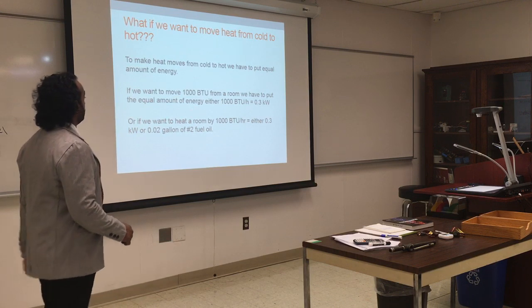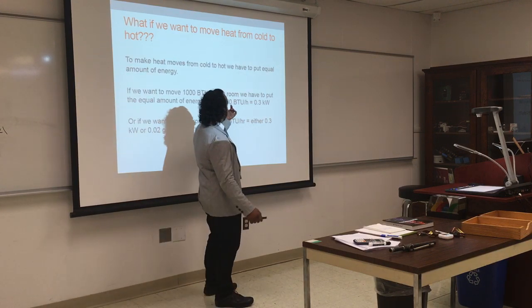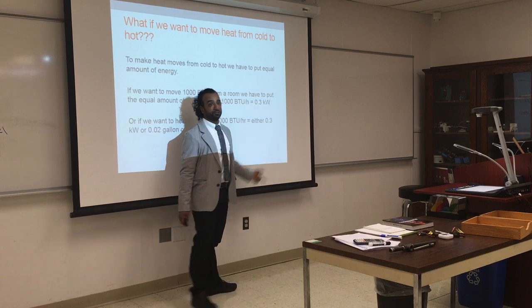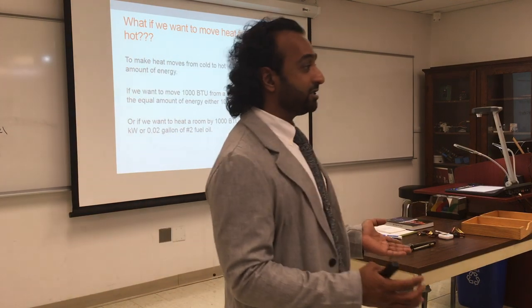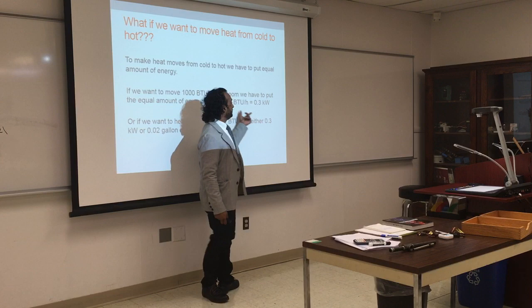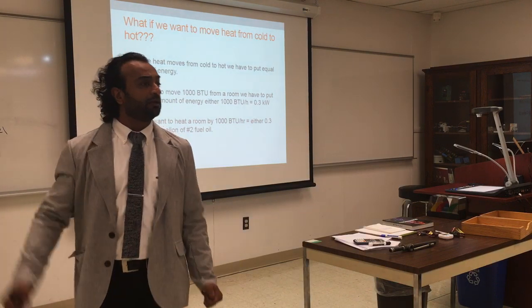If we want to move 1,000 BTU from a room, we have to put in an equal amount of energy, either 1,000 BTU or its conversion, which is 0.3 kilowatt. We said energy is the same thing, it's just different units, right? It's all energy. Your AC is not taking BTUs, it's taking kilowatts.